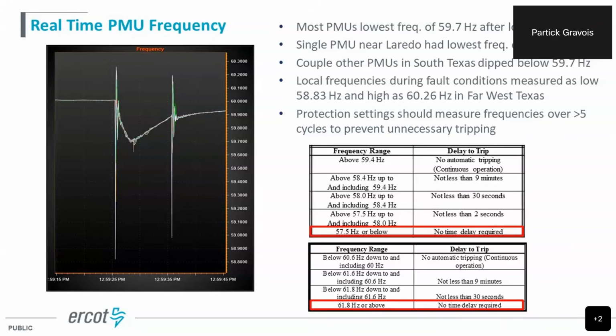So this is a screenshot from our nodal operating guides. This is kind of what I'm talking about, the 57.5 hertz or below. The way this is written, people seem to be taking this very literally and not providing any kind of delay to measure the frequency properly. So they're having this frequency, 57.5, that they see for one measurement for 2 cycles, and then they trip. We didn't see anything for the over frequency, but you can see it's kind of there as well.